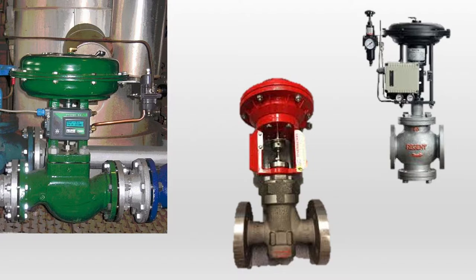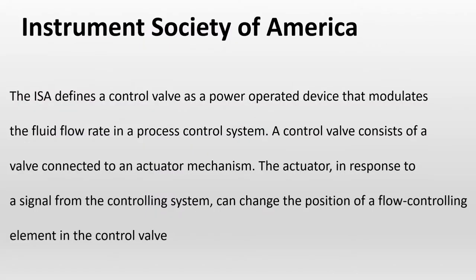So how do we define a control valve? If you want to define a control valve you have to refer to ISA — the Instrument Society of America. The ISA defines a control valve as a power-operated device that modulates the fluid flow rate in a process control system. A control valve consists of a valve connected to an actuator mechanism. The actuator, in response to a signal from the controlling system, can change the position of a flow-controlling element in the control valve.